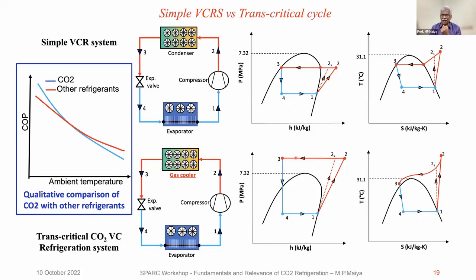As the ambient temperature comes down, this line comes down. You come into subcritical. So at lower ambient temperature, carbon dioxide does better; its COP is better than the conventional refrigerant. As ambient temperature increases, the COP degrades quite fast, faster than with the other refrigerants. So at high ambient temperature, carbon dioxide cannot compete in a normal way. So you have to see what we can do to improve it.